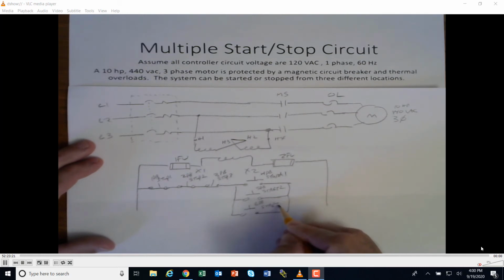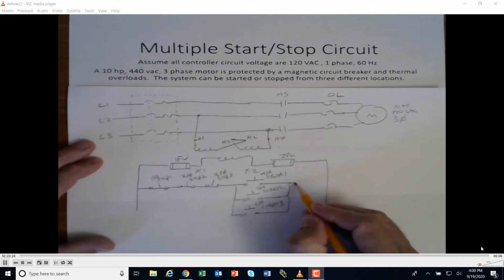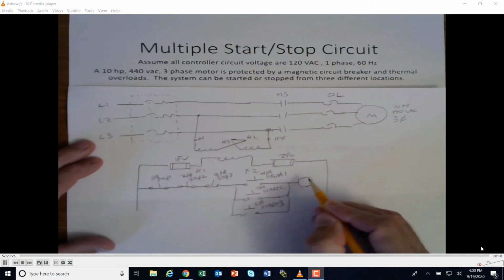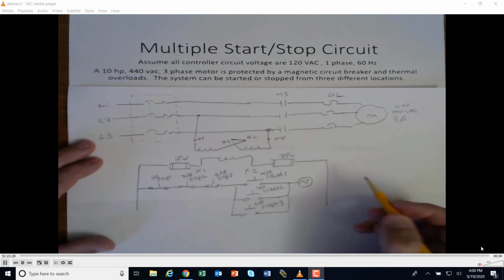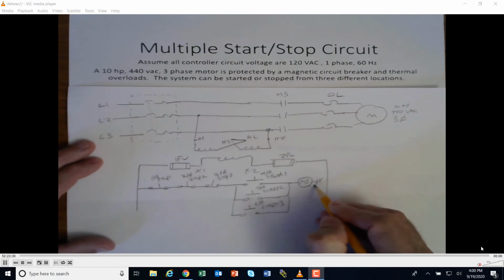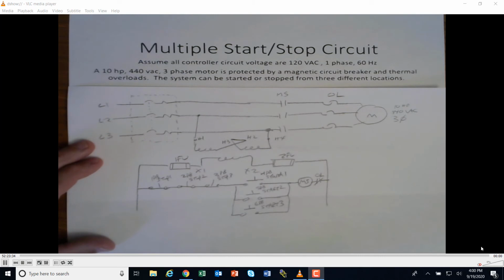What are these turning on? They're going to turn on my motor starter, and then I'll have overloads wired normally closed in here. So at this point, if I hit this, this, or this, it would come on. And if I hit this, this, or this, it would open - either one of those would open it.